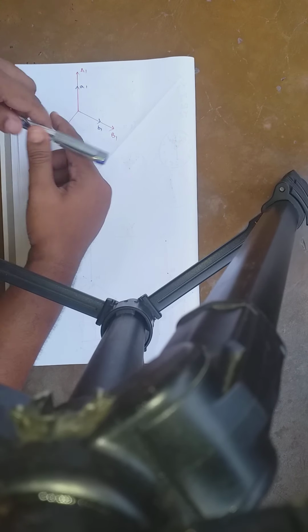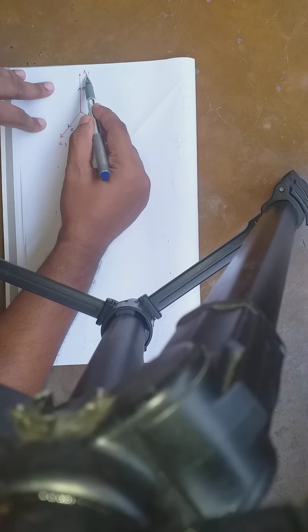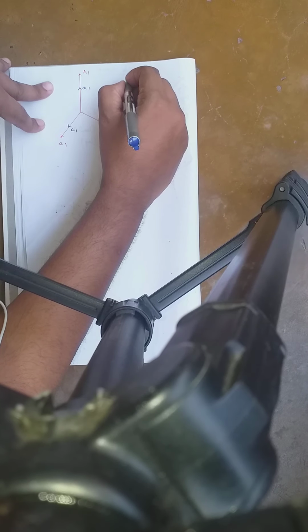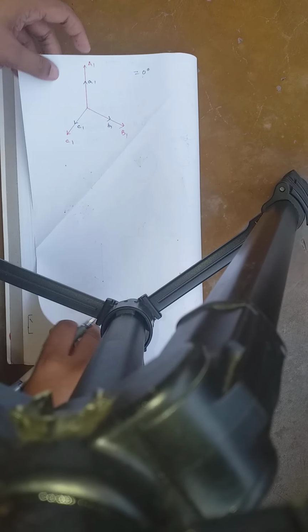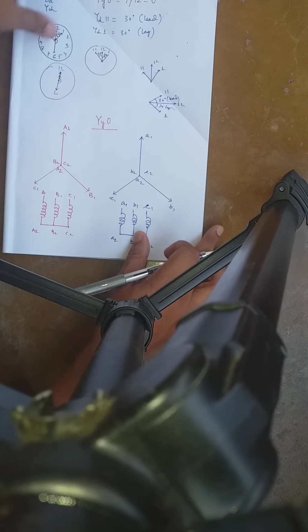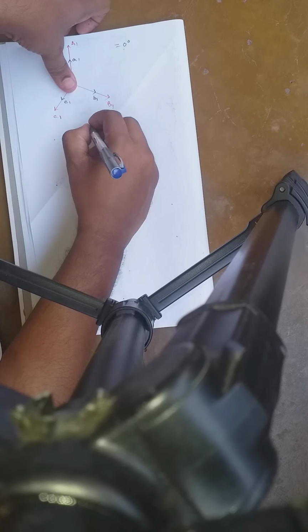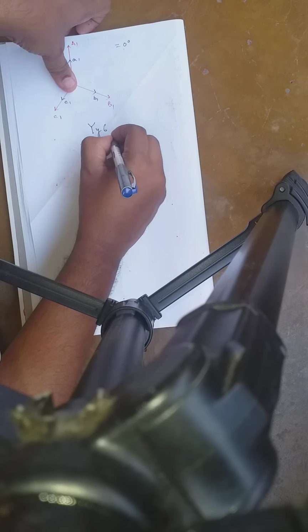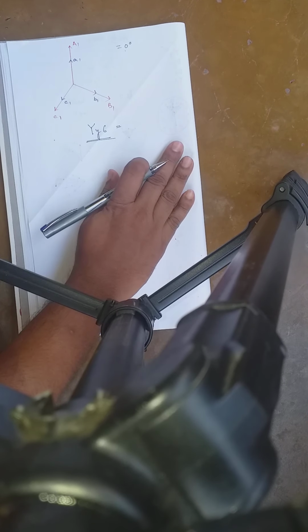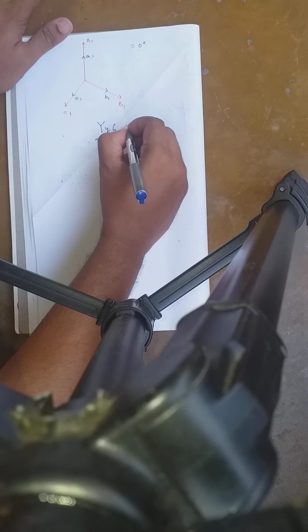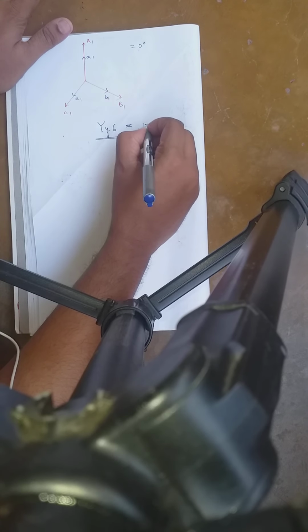So our key point is the phase difference, or the angular difference, between capital A1 and small a1 is equal to 0 degree. That is YY0. Now I am coming to YY6, most important and interesting. In YY6, the angular displacement between primary winding and secondary winding is 180 degree.